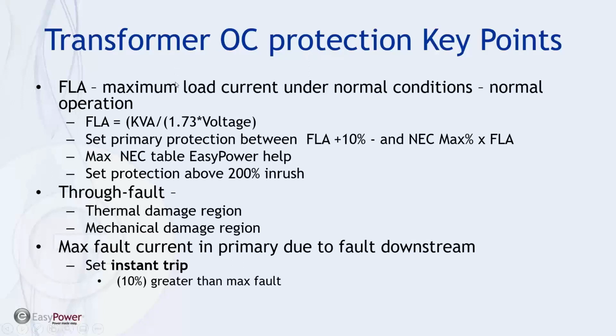Now, the key points to consider when we're talking about transformer protection: first, we have to determine the maximum load current under normal operations, and that's a standard equation that should be in everybody's cheat sheet. Settings of the relay, we set primary protection 10% above that number on the primary side, with the upper setting being suggested by the NEC guidelines, and I'll show the chart here shortly, at some percentage based upon certain conditions or stipulations about the transformer itself, but a certain percentage above that full load current calculation. And these limits are actually built into EasyPower.